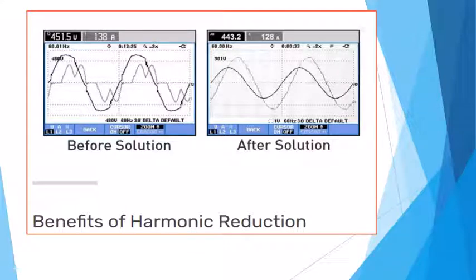So this motor was 451 volts times 138 amps times 1.73 for all three phases. So that was 107 kilowatts being drawn on that. But if you take the same load with the filter, you take 443 times 128 times 1.73. That's 98. So you subtract those two. That's the difference in losses that you're getting charged for.